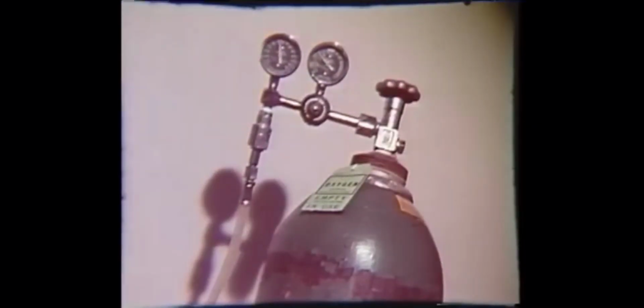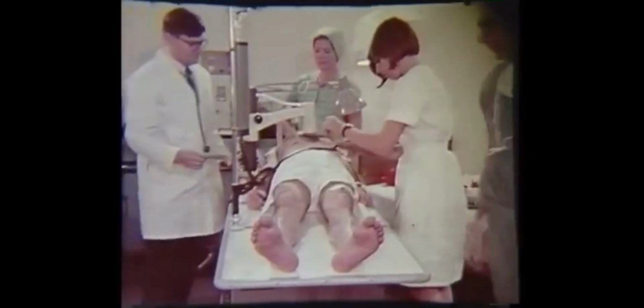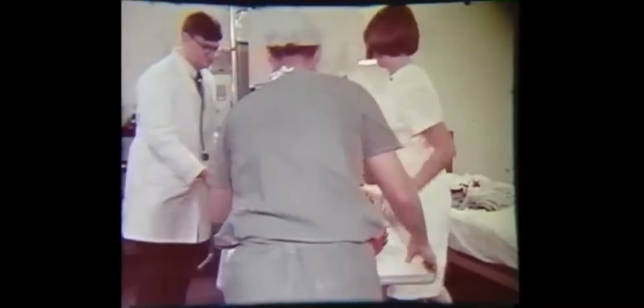If wall oxygen had not originally been available, one E-tank would have been used while awaiting a large external tank to receive the wall oxygen hose. Each of the two E-tanks will provide oxygen for approximately 15 minutes, or a total of 30 minutes. If no external oxygen source were available, alternating between and replacing E-tanks would provide adequate oxygen. The team leader confirms the condition of the patient, and with assisted oxygen-supplemented ventilation, intravenous fluids running, and ECG trace visible, MAX can provide all supporting modalities, including cardiac compression in transit.